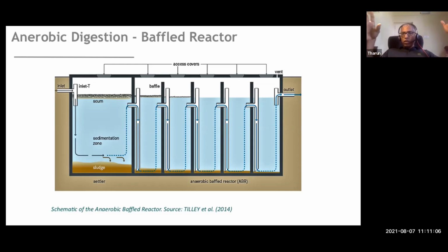So typically it costs around 50 to 60,000 rupees per KLD, civil cost for this. One-time cost, but that's to build these big tanks. The top area, depending on the technology, can be completely reused. Some technologies you can't reuse, DEWATS you can reuse, some technologies you can reuse, but I'll come to that. But fundamentally, this is how the tech works. So you go through multiple chambers and large tanks, and this is a one-time capex-heavy investment. You put all the pipes in, multiple tanks. Design is very complex. You have to get a very good designer to do this. It has to be executed very well. All these pipes should be at the same level. There's a lot of intricacy, a lot of science goes into this. It's not as simple as it looks.